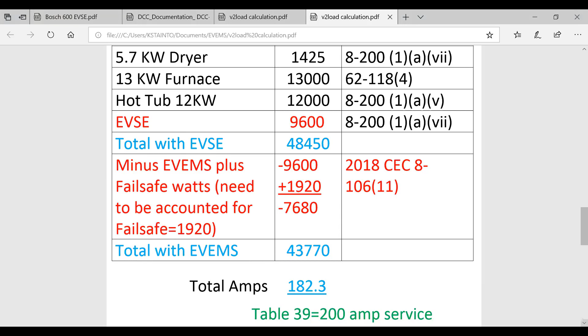So we're able to take 7,680 watts off our total now, which leaves us with 43,770 watts in this case. We do our little calculation, divide that by 240, and it turns into 182.3 amps. Referring to table 39 again, as you can see, we can still maintain that 200 amp service.